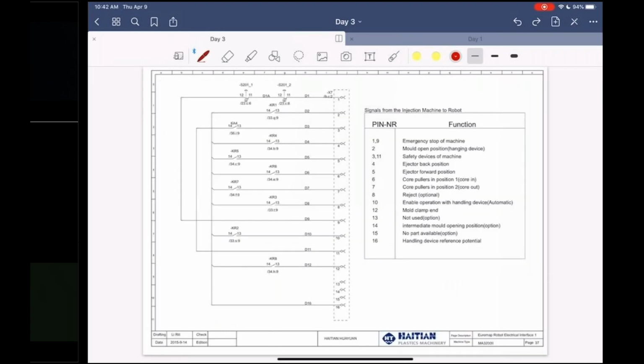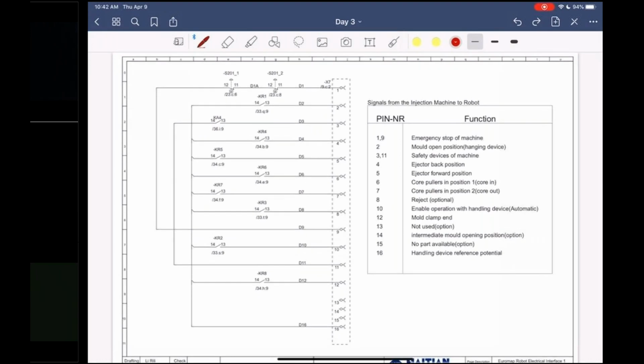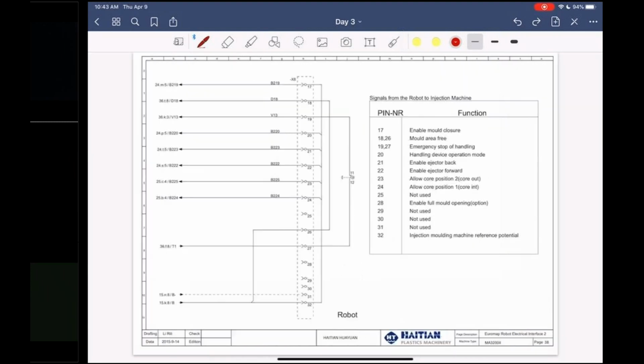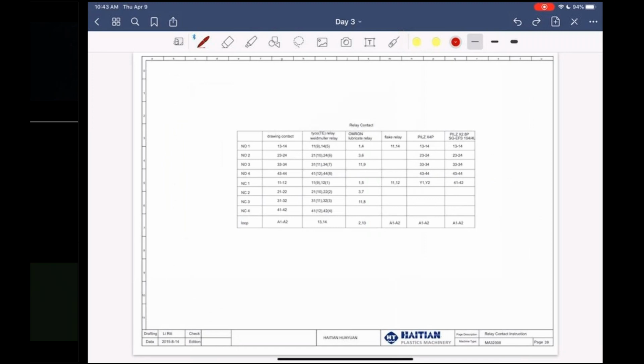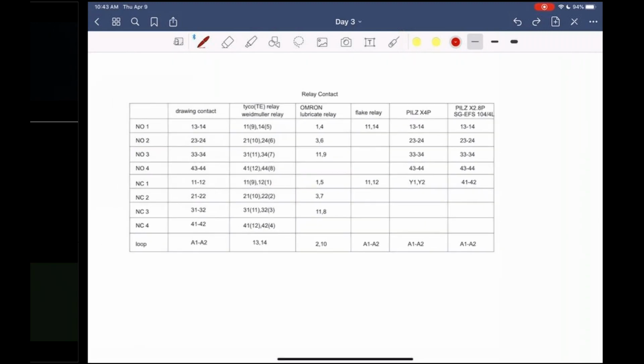This is your Euromap 12 interface. I believe most of the machines are going to start coming in Euromap 67. The only difference between Euromap 12 and 67 is this one's a 32-pin connector, for one thing. 67 is a 50-pin connector. The 32-pin has two rows of connection points. The 50-pin has 3 rows per input and output. The Euromap 67 has dual channel e-stops and dual channel safety door signals, whereas the Euromap 12 only has single door signals and e-stop signals. So this is signals from the robot to the machine, and these are from the machine to the robot. And this is just a relay contact information block.